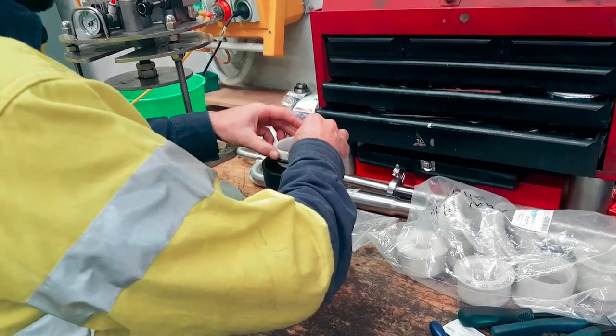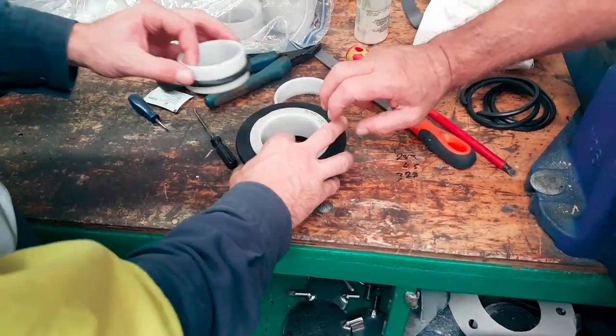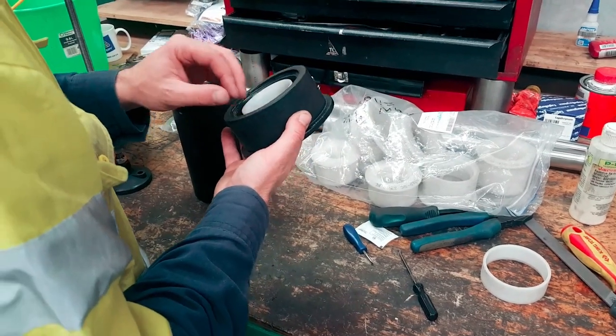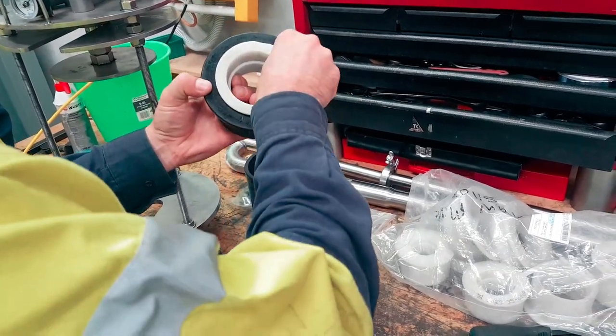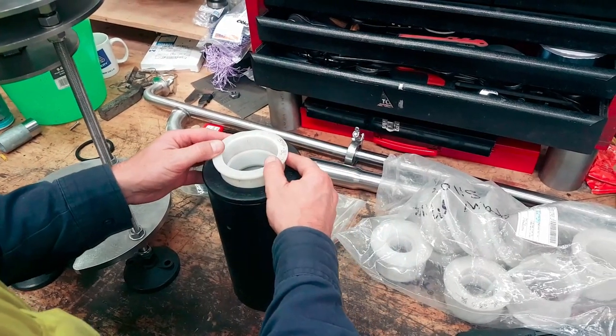Come back into your tool again. Oh, no, other way. That's the one. Taper, tapers down. Yep, you've got it. Now that's where you come undone. That sleeve flips over like that, and the guys aren't aware of it, and they put the press on it, just crushes it.